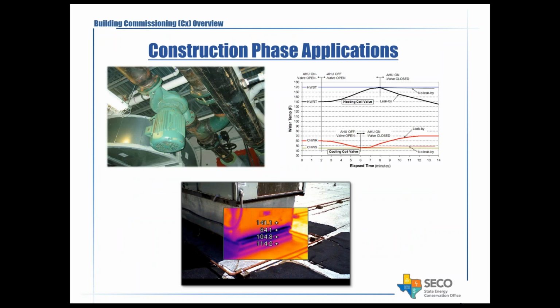Some of the things you will see in the commissioning process: hopefully the commissioning agent, if involved in the construction phase, will be able to identify a few issues that could be addressed. For example, on a rooftop unit, a thermal scan was done, and they saw a slight leak at the seam of the transition. That was identified as a repair item.